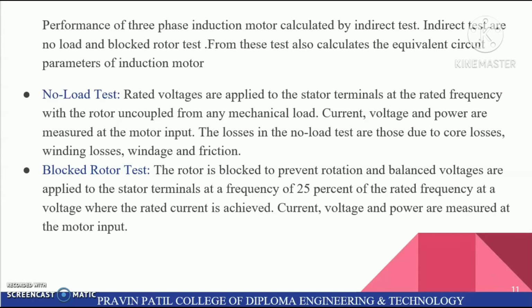So in the no load test, rated voltage is applied to the stator terminals at the rated frequency, with the rotor uncoupled from any mechanical load. Current, voltage and power are measured at the motor input. The losses in the no load test are those due to core losses, winding losses, windage and friction.